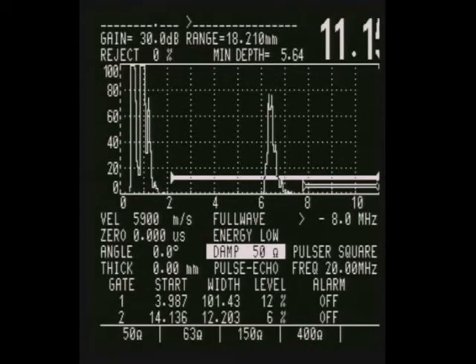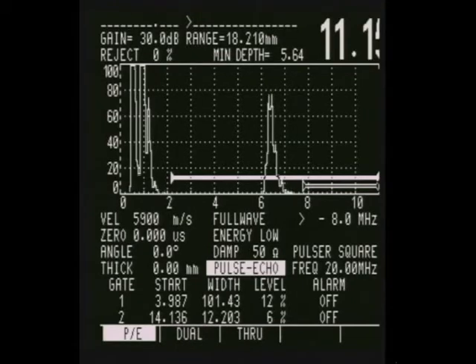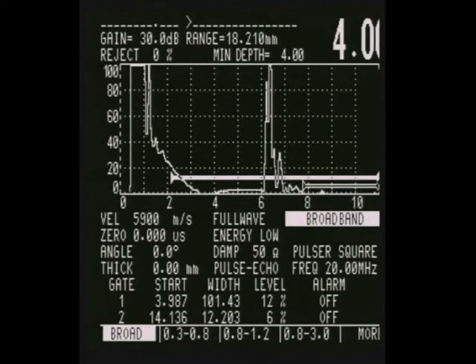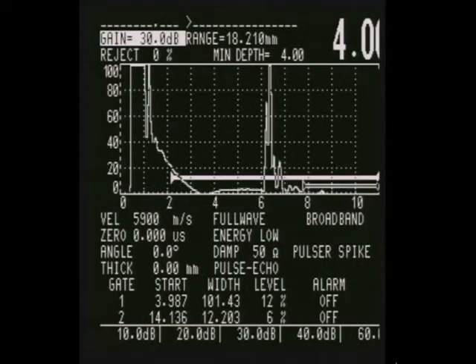Damping is at 50 ohms. Pulse echo. So we're using a single crystal here. So pulse echo is a technique to use. And I'm going to use broadband to start out with. And I'm going to get rid of that square wave. It's a totally useless thing unless you're selling an Epoch 4.